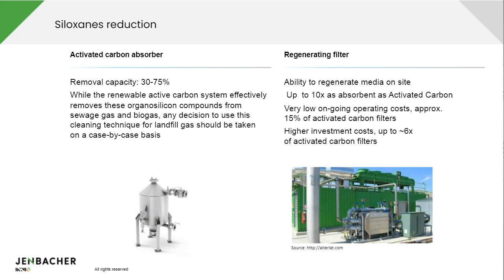If you do have very high concentrations of siloxanes or sulfur, then you might want to go with a regenerating filter where the absorbing characteristics are also very good, but the main advantage is that you have low ongoing operating cost. In this case, it says you're approximately 15% of the activated carbon filter, since once the media is saturated, you can regenerate it, and then you can reuse it, and you don't have to have the replacement of the media, the absorbent. So these are obviously more expensive, higher investment cost, approximately 5-6 times more than an activated carbon absorber, but you have lower operating costs.